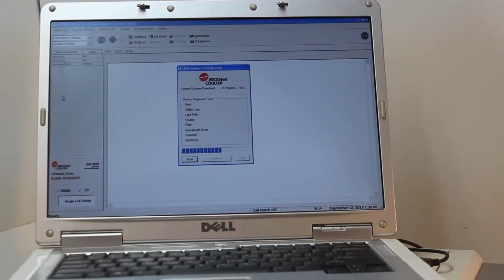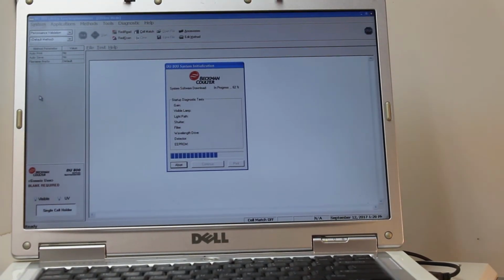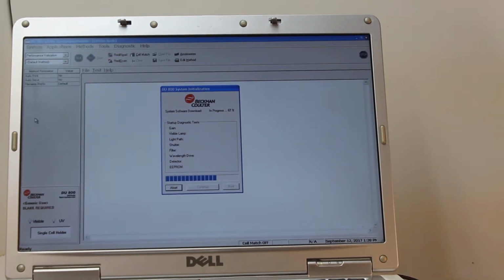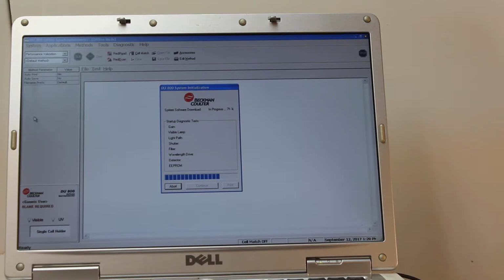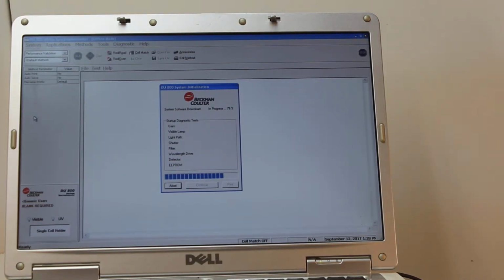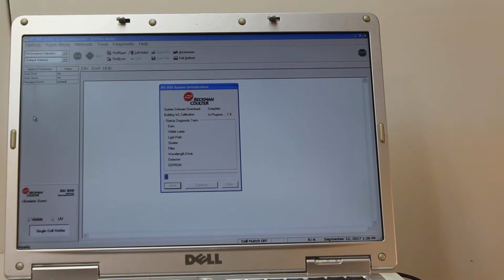many biochemists, chemists, and the pharmaceutical industry love this kind of lab equipment. It has a very wide wavelength range, 190 nanometers to 1100 nanometers, and also very good wavelength accuracy. At a wavelength of 651.1 nanometers, it has a wavelength accuracy of 0.2 nanometers, and over the full range the wavelength accuracy is 0.5 nanometers, which is very good. It also has very good photometric accuracy and stray light performance.